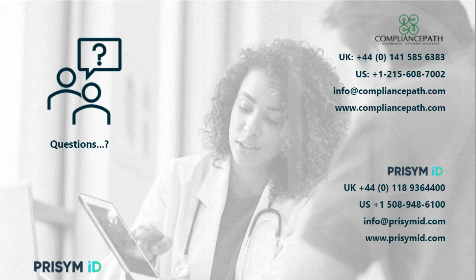Well, mitigation is all about leverage as part of it. So if you're moving into that arena, if you're looking to a supplier that's going to provide you with a commercial off-the-shelf solution, like Prism ID here, as part of our package that we deliver, we will deliver documents, test documents, functional specifications, OQ documents, installation qualifications, test summary reports, traceability matrix.